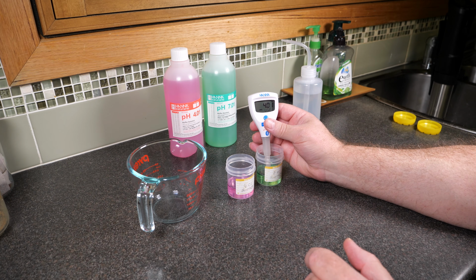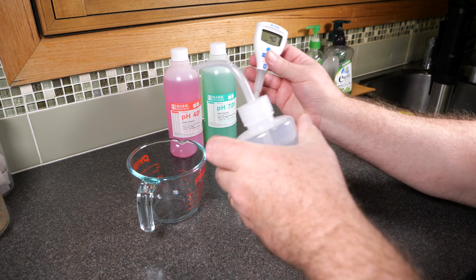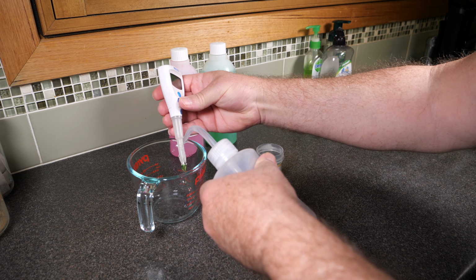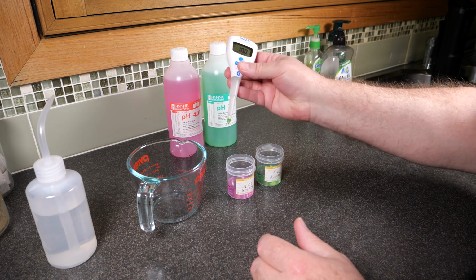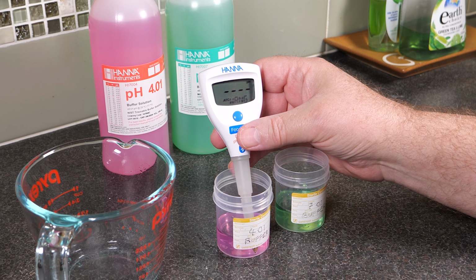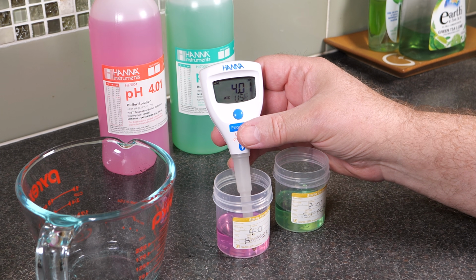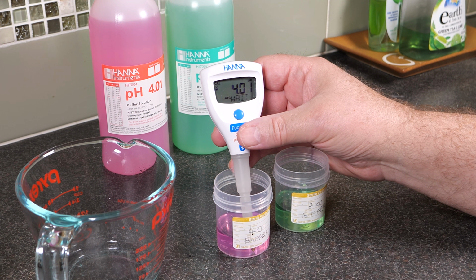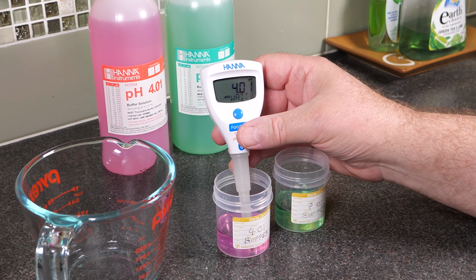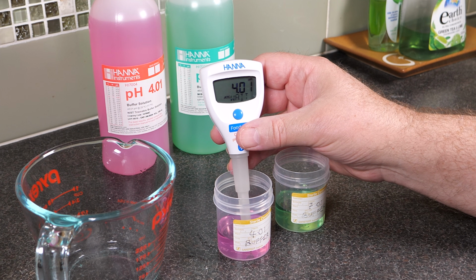There we go. So it's told me to use the 4.01, but in between, always rinse off the probe with the distilled water, then pop it into the 4.01. Then it figures out, yes, it's going to use that one next. There we go, so it's now calibrating while the little hourglass is still flashing, and it tells us to wait. Now this may take some time. Now I wasn't sure it was working, and then all of a sudden, bingo boingo, it saved the calibration.